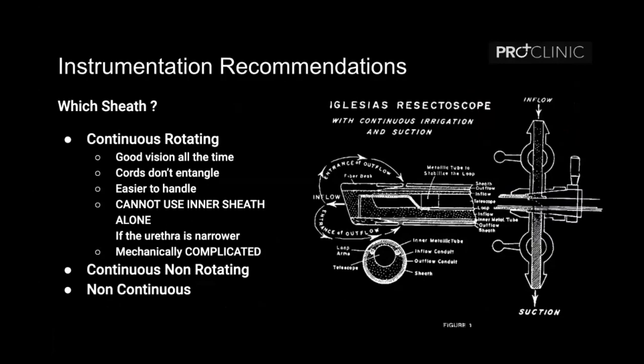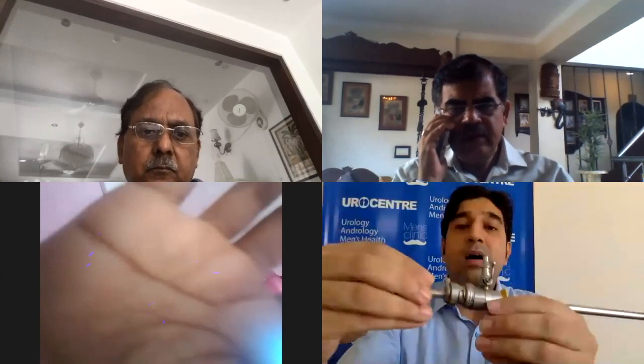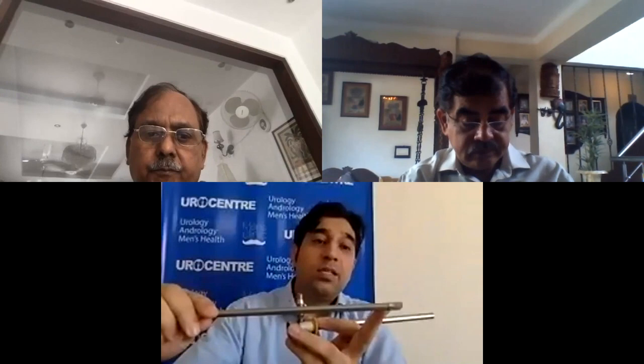Coming to instrument recommendations — which sheath should a resident use? We are now using the continuous rotating type of sheath. I will stop sharing the screen and give a physical demonstration. So here is the assembled resectoscope sheath — this is the continuous rotating type. Here we can see the complicated tip of the inner sheath and the outer sheath. Just by looking at the outer sheath we can say this is a continuous rotating type of resectoscope.